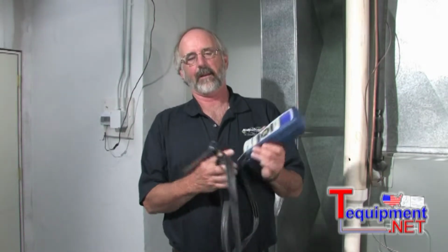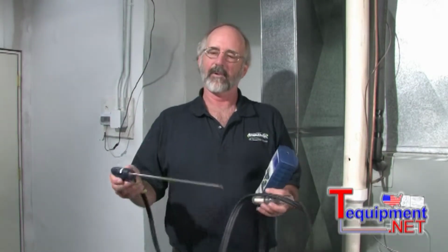Specifics of the instrument. We've turned the instrument on again by pressing the power button. It'll go through a 60-second countdown. It's important to make sure that during that 60-second countdown the probe is outside any places where it might be pulling flue gases. It won't hurt anything, but it'll just throw the zero off on the sensors.